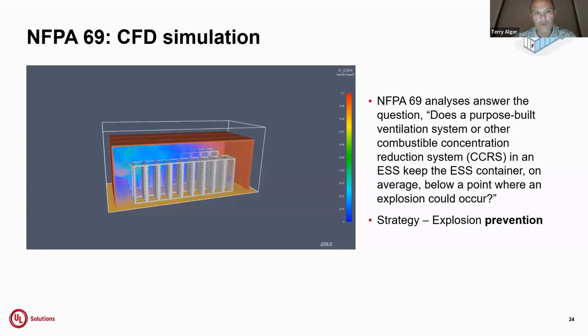So the strategy here is to prevent an explosion from happening in the event of venting or some kind of thermal runaway inside your battery energy storage system. It's often quite a robust simulation, and we find that the CFD can do quite a good job of predicting the flammability levels of the gases inside the battery energy storage system, especially if you combine it with some validation tests at the module or rack level.